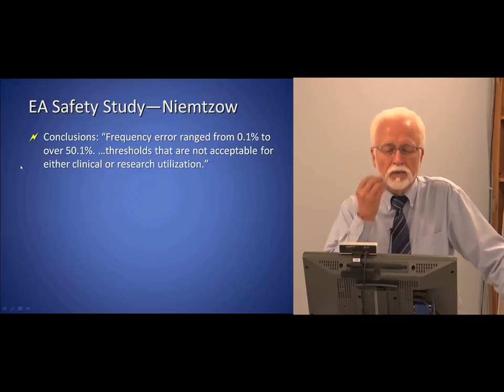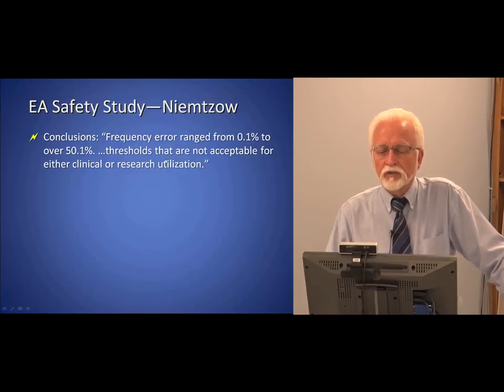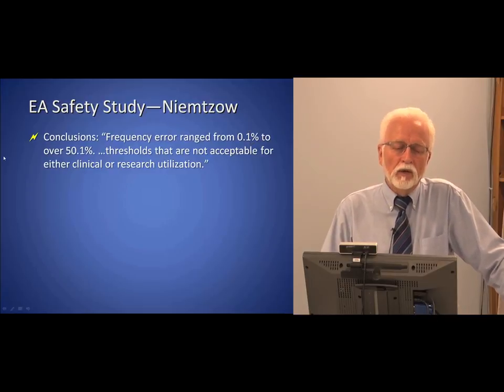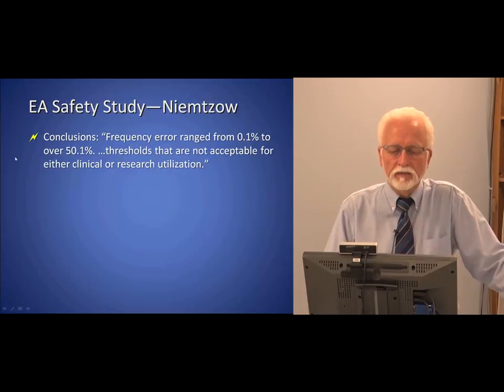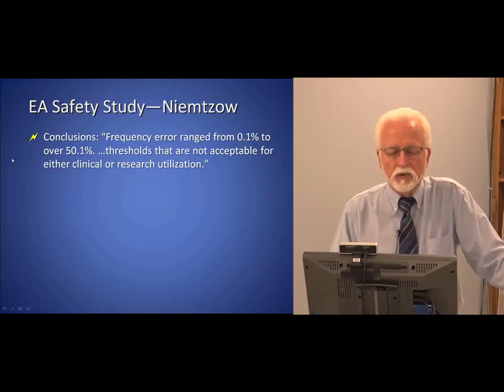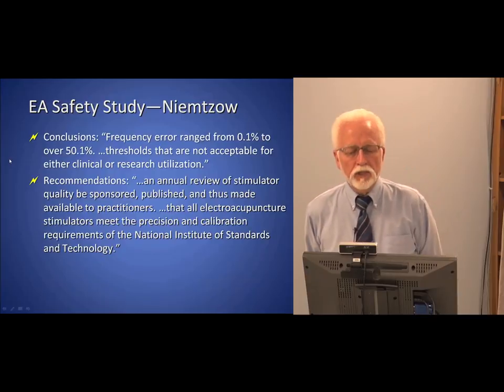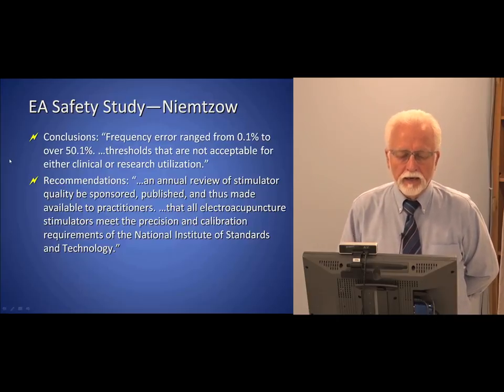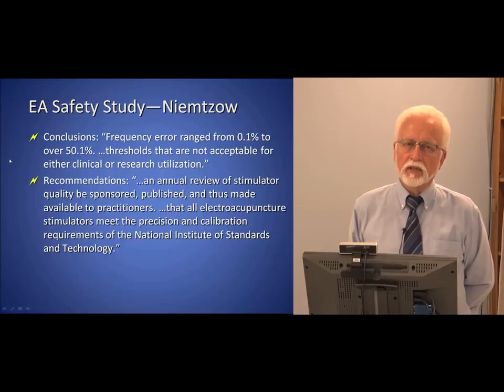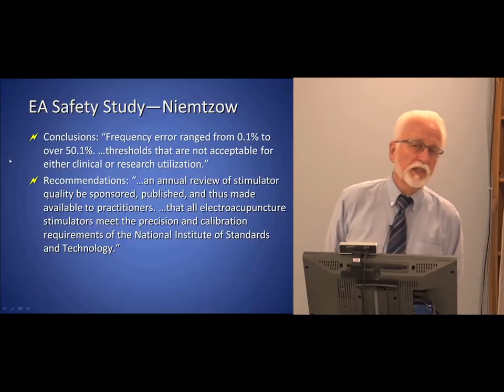Now, Niemzow's study was probably a little bit stronger even because he tested 6 devices, remember, and he found the frequency error ranged from 0.1%, so less than like 1/10 of 1%, which is pretty low, to over 50%. So some of the devices were way off in their frequency calibrations. And he says these thresholds are not acceptable for either clinical or research utilization. He recommends an annual review of stimulator quality, sponsored, published, and thus made available to practitioners, that all acupuncture stimulators meet the precision and calibrations requirements of the National Institute of Standards and Technology. He was trying to prod government to get involved in doing some testing.